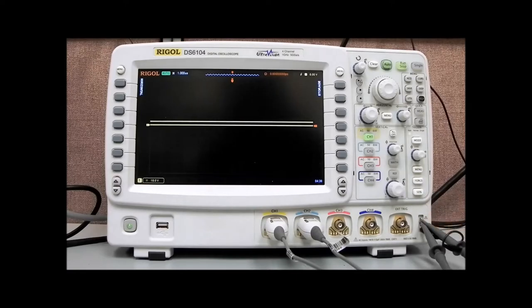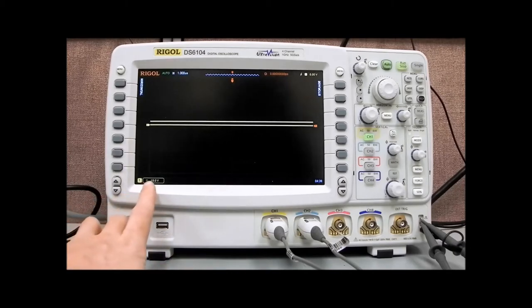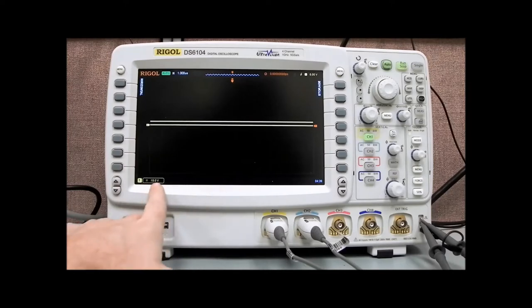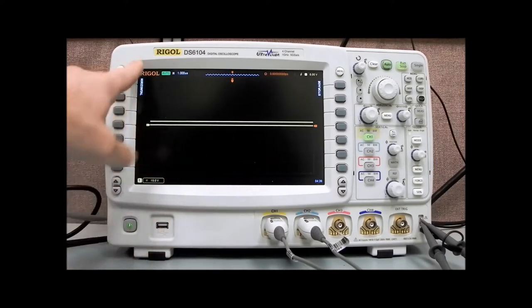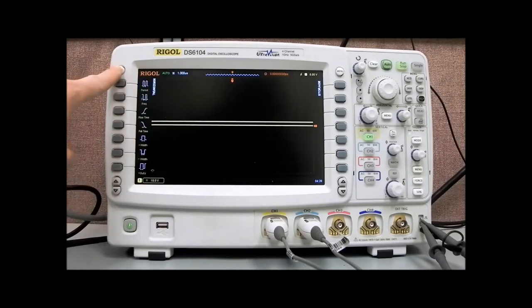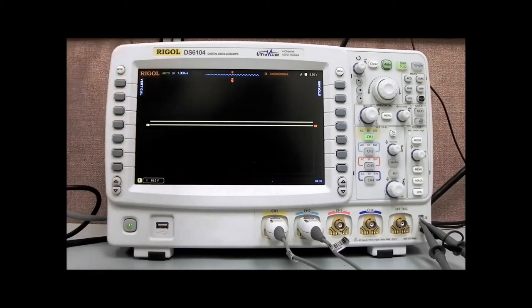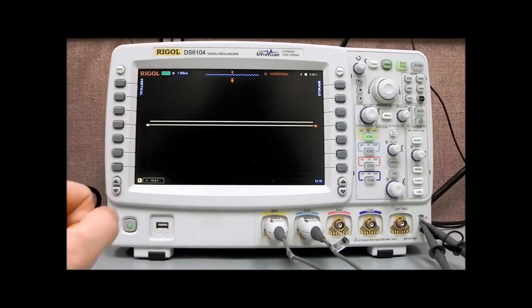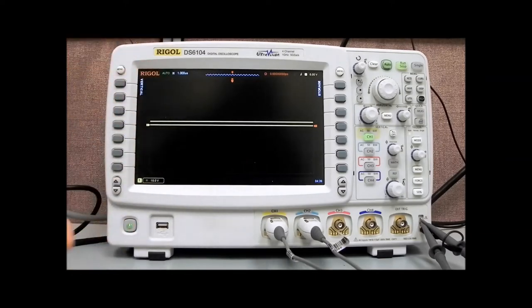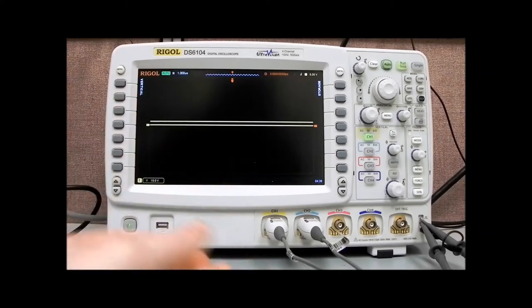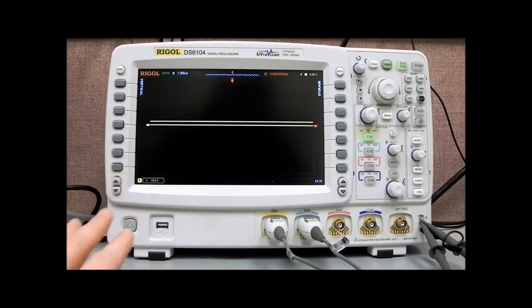I'd like to describe in more detail what we see on the screen for the DS6000. On the lower left-hand corner, we have the channels and their voltage settings. We have a quick menu on the left-hand side with horizontal and vertical measurements. We have the auto trigger, which denotes when the instrument is triggered and the trigger mode enabled. When it says auto and the green light is flashing, we're doing a rolling trigger. Once we've collected data in memory, it starts over again.